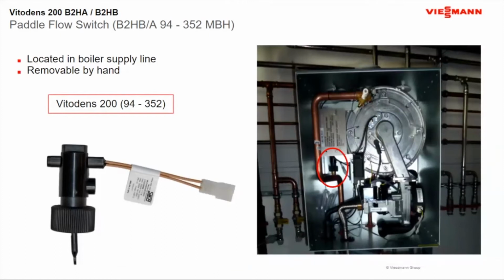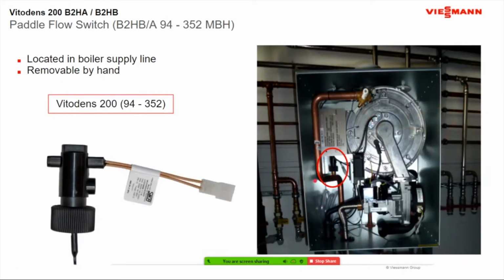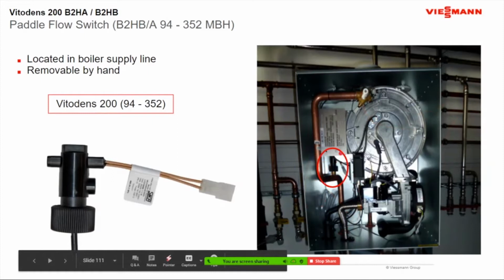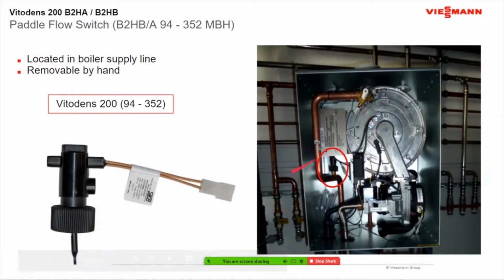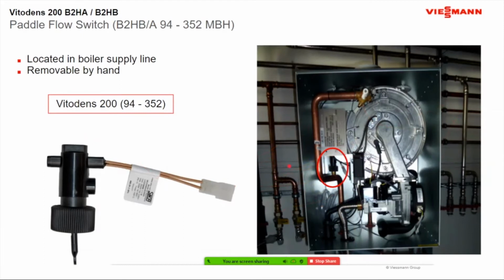On the smaller ones, excuse me, we have a flow switch. The flow switch is activated by your pump. So now you can see that the water comes through the boiler, comes down and goes down. So your actual arrow on these things is pointing towards the back. There's an arrow on the top and you can see it once you have it out. And I always tell people, if you're ever taking a look at these, make sure that wire is coming out towards the pipe, the brown wire, and then that will ensure that this is going in the right direction.